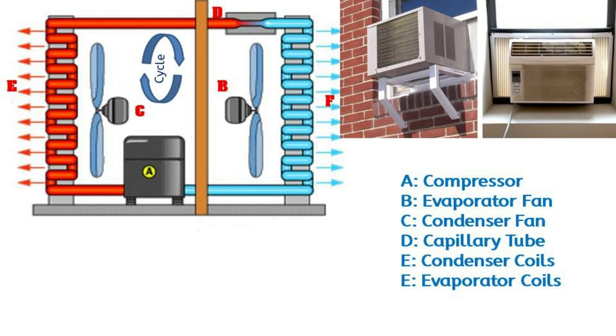In the condenser, refrigerant vapor condenses by dissipating heat to the cooling medium or atmosphere. The liquid refrigerant coming out from the condenser passes through the capillary tube, where it expands, thereby reducing the pressure to evaporator pressure. The lower pressure, lower temperature liquid refrigerant then flows into the evaporator, where it gets evaporated by extracting the heat from the air which is drawn into the evaporator cabin from the room to be cooled.